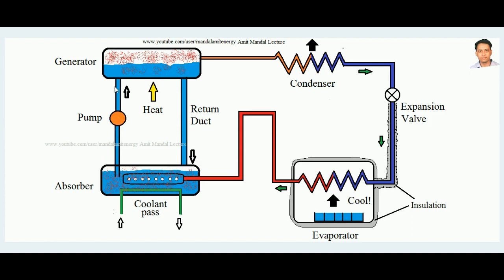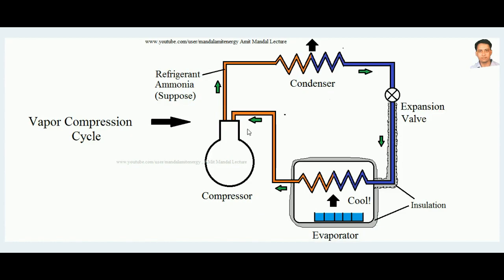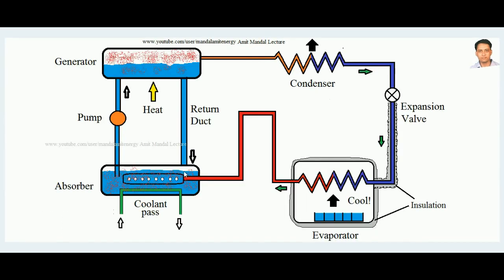By the help of a pump, the aqua ammonia strong solution is sent to the generator. In the generator, heat is supplied. Ammonia is soluble in cold water, but when heat is supplied in the generator, the ammonia is liberated and collects over the top of the liquid water at high pressure. This accomplishes the job of the compressor — taking ammonia at low pressure and delivering it at high pressure.